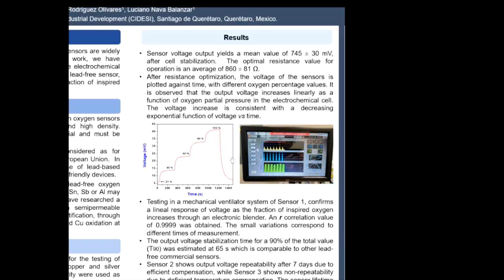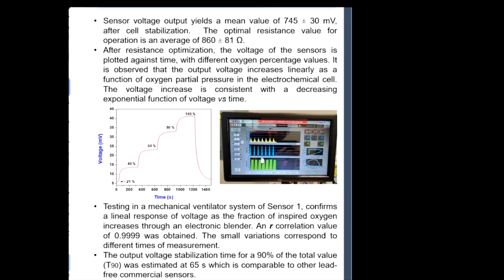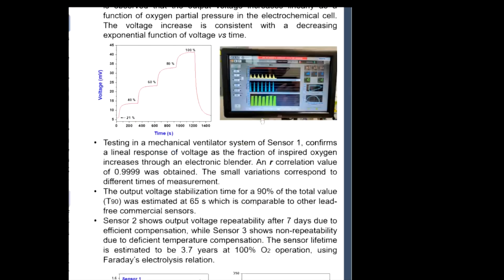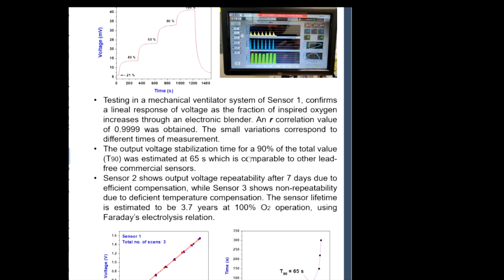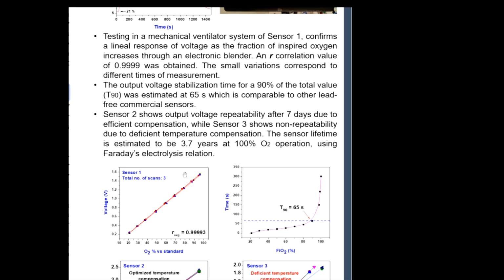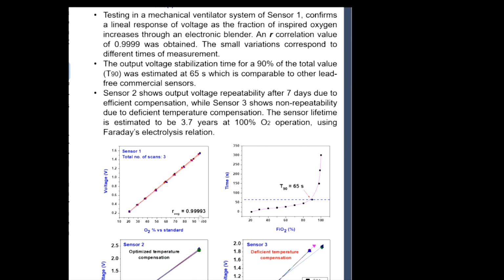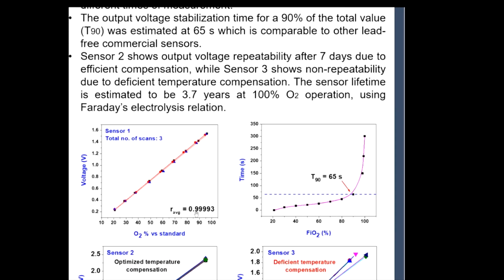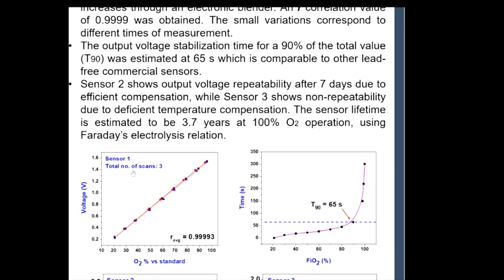After this testing in the laboratory, we transferred the sensor to a real setting, which was a mechanical ventilator system, where we used defined parameters such as flow, volume, and pressure, as you can see here in the figure. After this testing in the mechanical ventilator system, we found that there's a linear relationship between the voltage value and the fraction of oxygen, where we used the commercial gas analyzer as a reference. We found a linear correlation with a value of 0.99993 for a total of 3 scans.